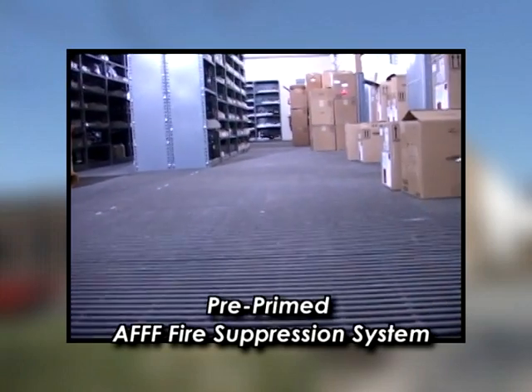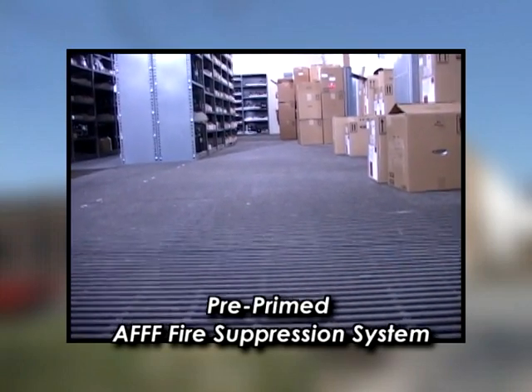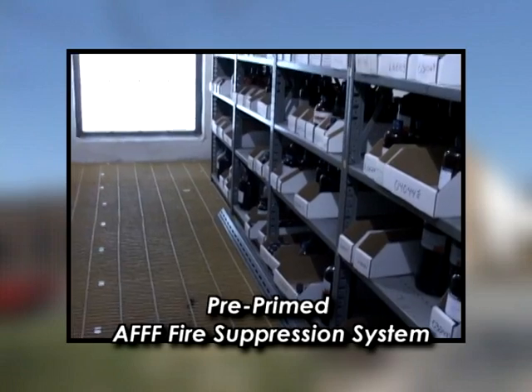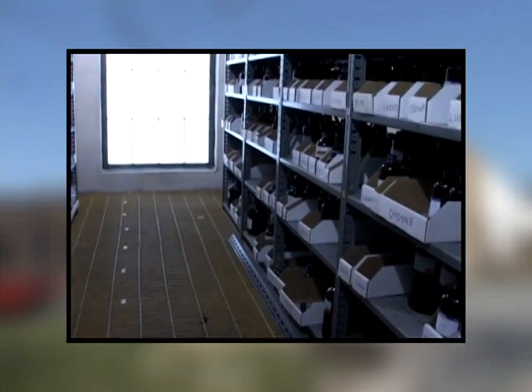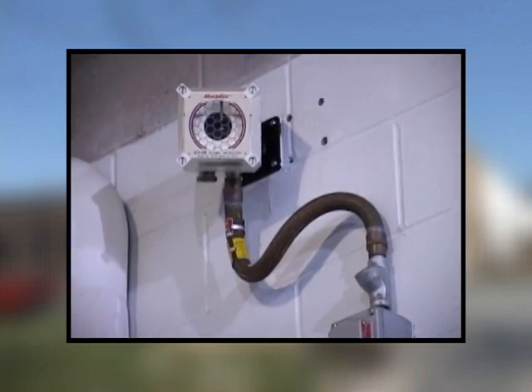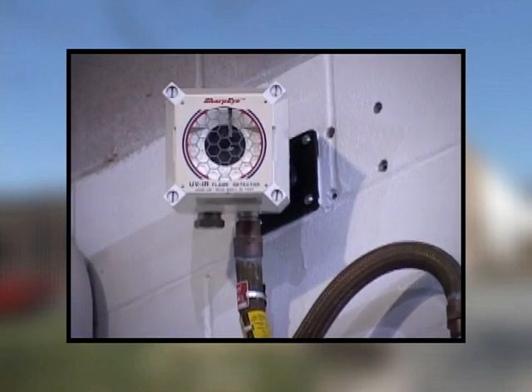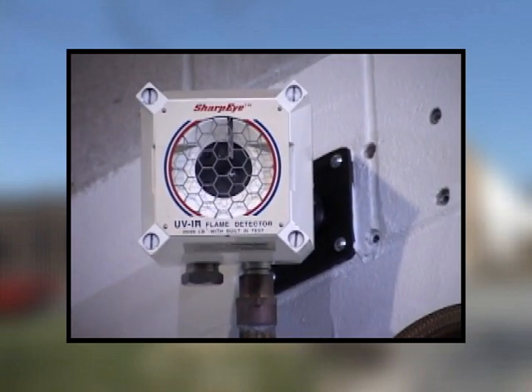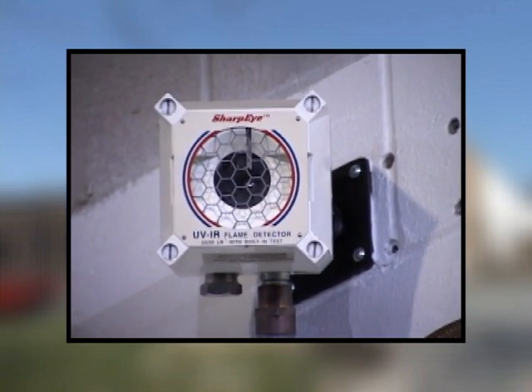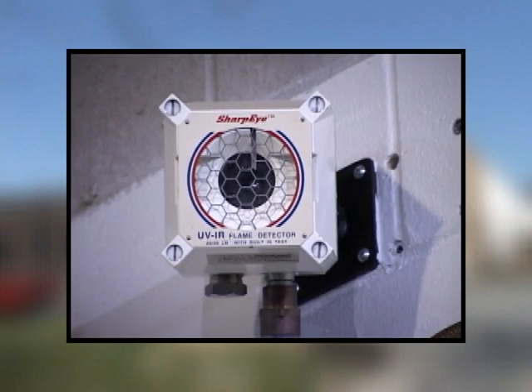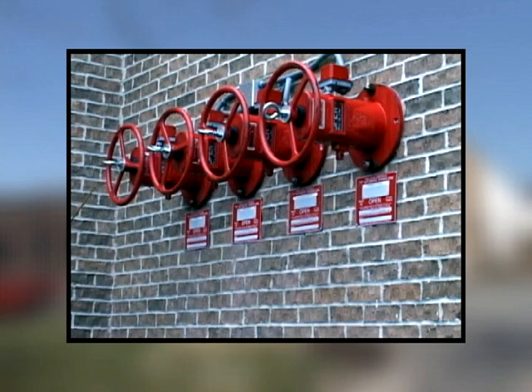Heat from a developing fire will cause the release of the AFFF solution at the local area closest to the source of heat. UV-IR detectors located throughout the space will also signal the system. These serve only as an early warning device to summon emergency response personnel to the site based on a signal received from the fire alarm system.